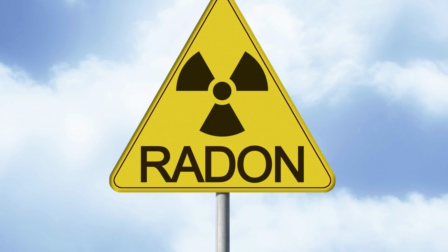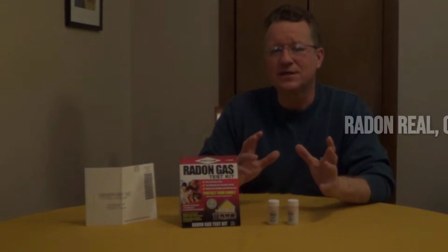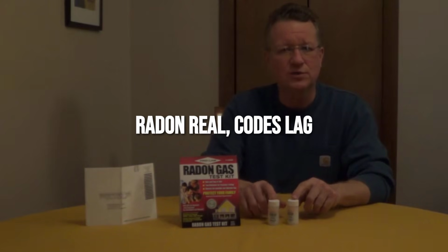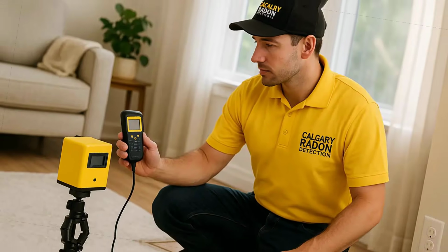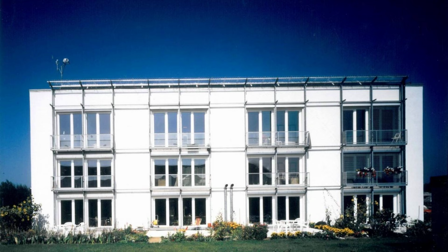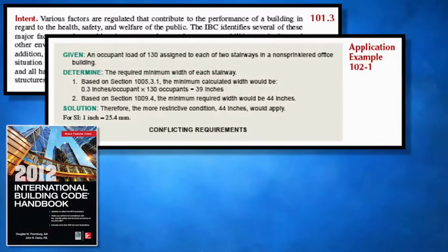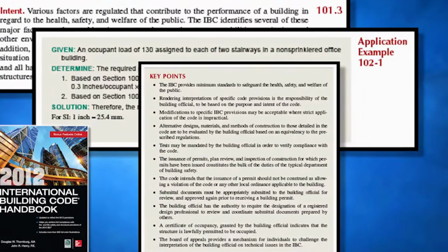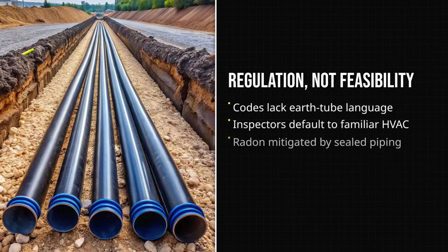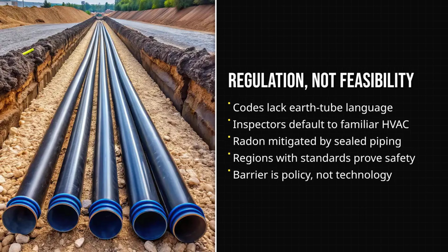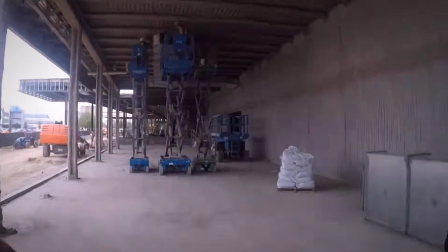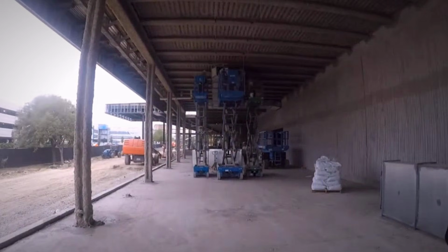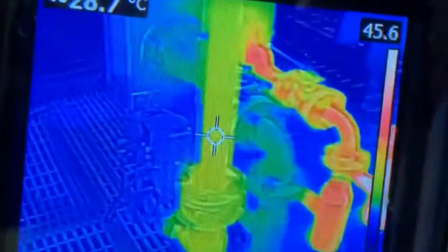One of the primary concerns raised is radon. Radon is a naturally occurring radioactive gas that can accumulate in enclosed spaces, and it is linked to lung cancer. This concern is legitimate. However, in regions where earth tube systems are more common, proper design standards have already addressed these risks. Sealed piping systems, proper drainage, and filtration can effectively mitigate these issues. In other words, the problem is not the system itself, but how it is implemented. And where proper standards exist, the system works.